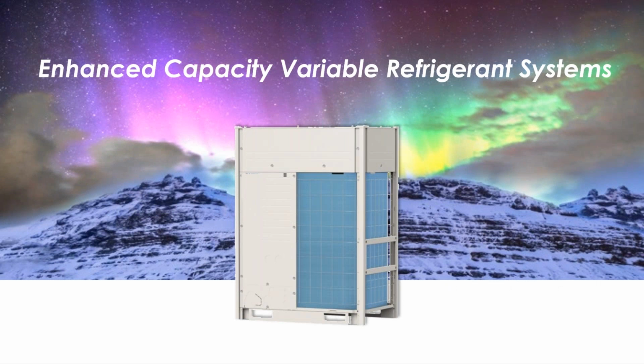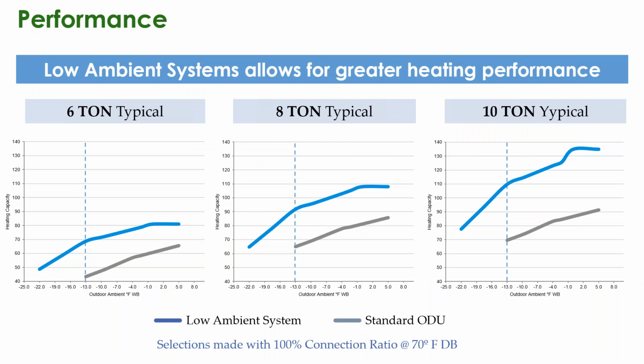So finally, the other common way that has been happening for a little over a decade now, I think, is enhanced capacity variable refrigerant systems. These are systems that are designed specifically to operate in cold climates and do so better than their standard efficiency counterparts. So the low ambient systems allow for increased heating performance, as you can see by the charts there, typical 6-ton, 8-ton, and 10-ton, anywhere from 40 to 60% more capacity at -13 than their standard counterparts.